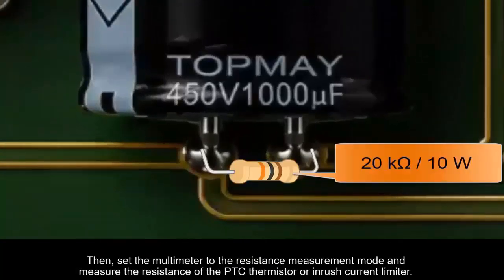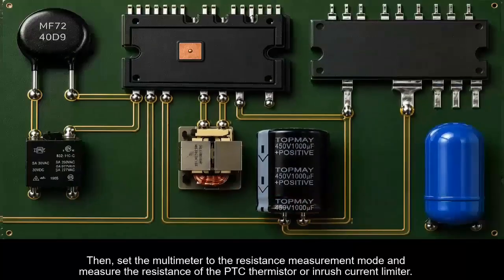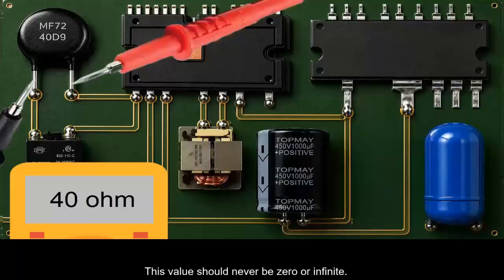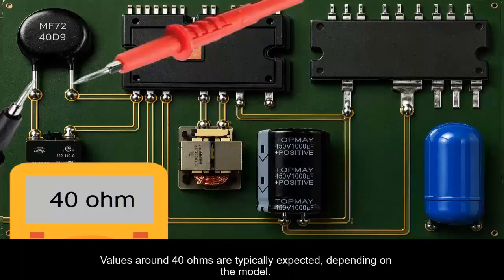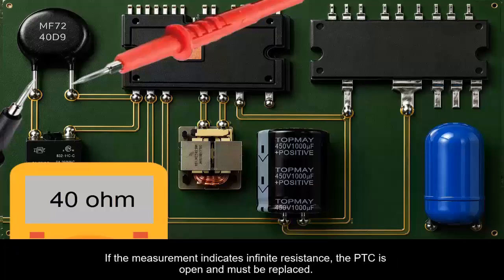procedure. Then, set the multimeter to the resistance measurement mode and measure the resistance of the PTC thermistor or inrush current limiter. This value should never be 0 or infinite. Values around 40 ohms are typically expected, depending on the model. If the measurement indicates infinite resistance, the PTC is open and must be replaced.